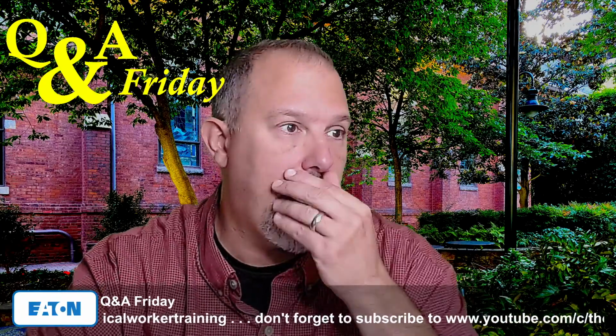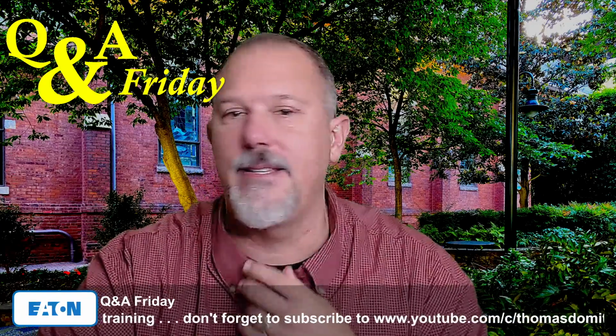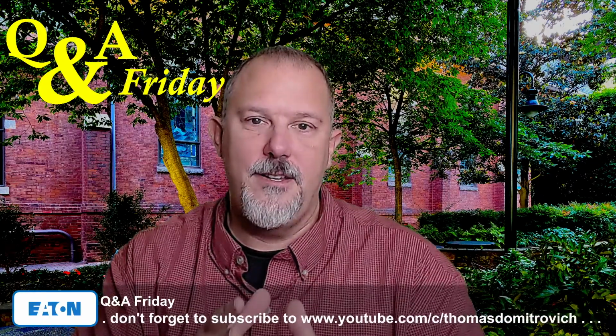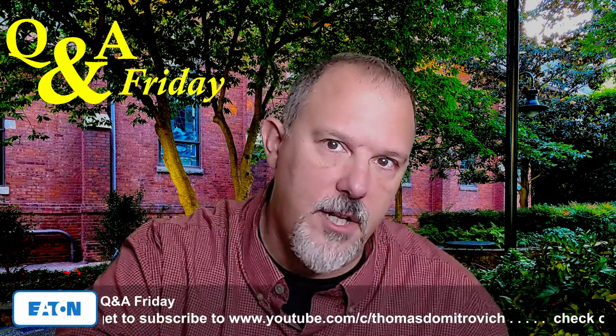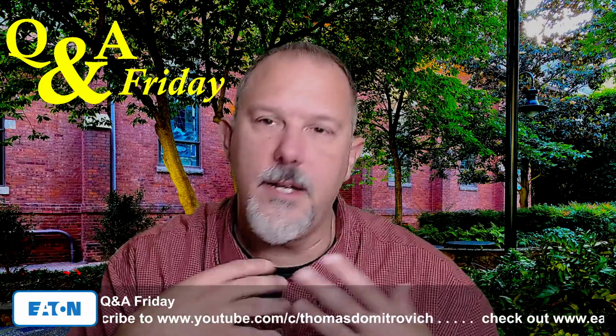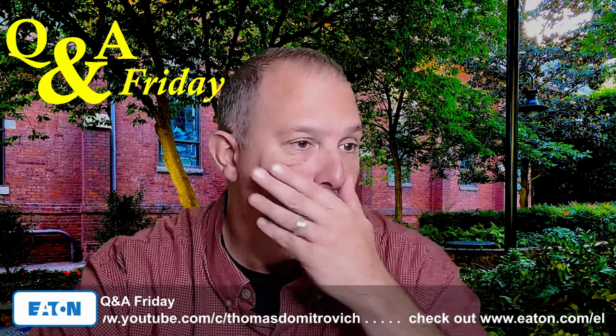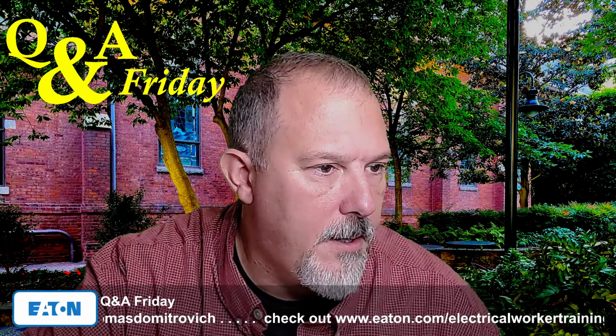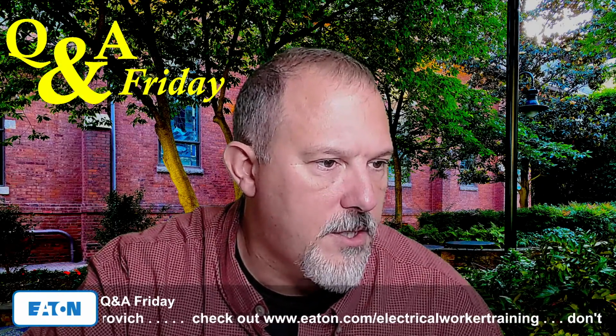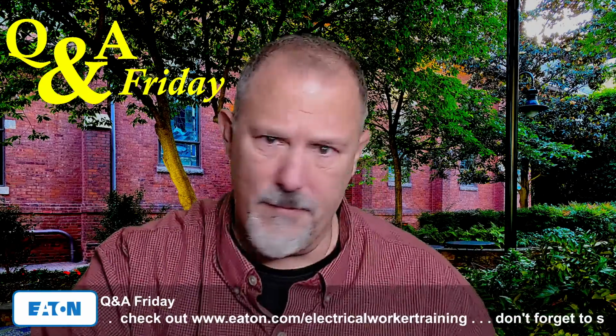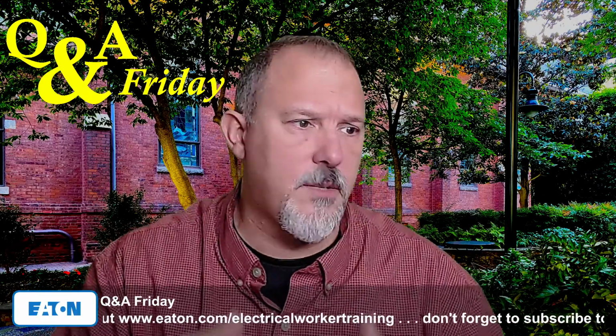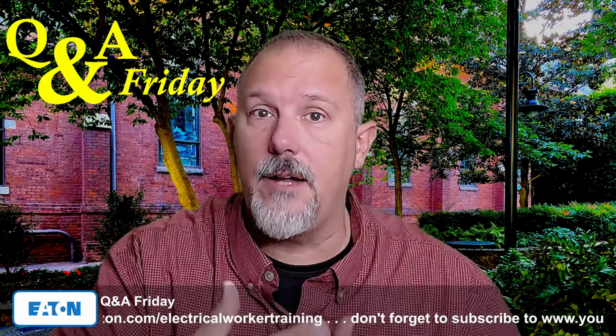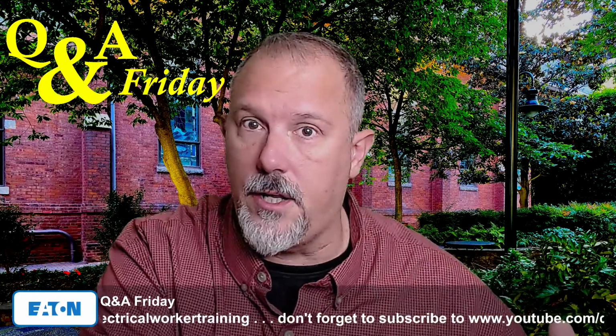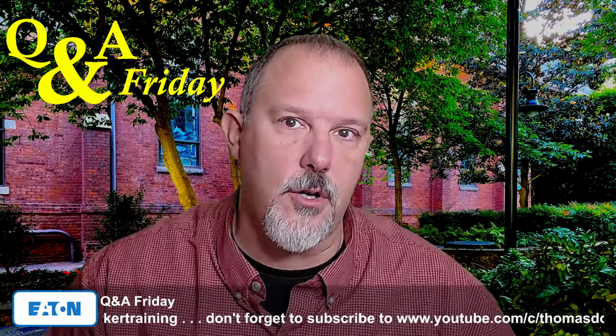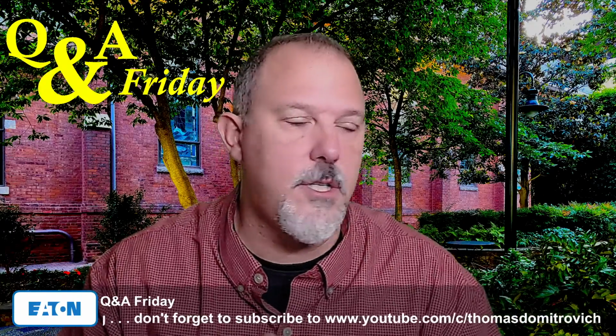Really good question, though. I never really looked at that concept that a series rating is only associated with a circuit breaker. SCCR is rated. Wow, we got a bunch of questions in here. Hold on. Does this relate to current let-through? Some busway might have breakers as plugs, so something to keep in mind. Absolutely right. So if your busway has a breaker as a plug, you can change that breaker out. There's plugs that you can put in that have a fuse in it if you need a higher short circuit current rating. So there's a lot of things you can do there as well.